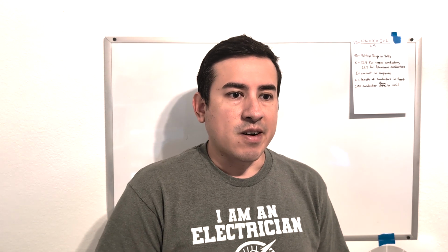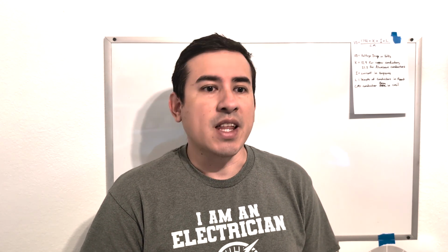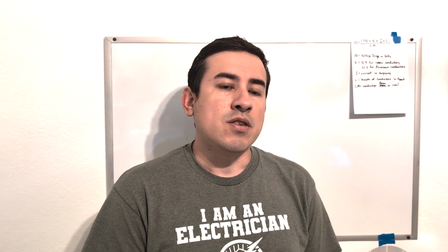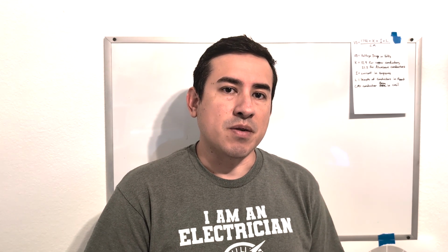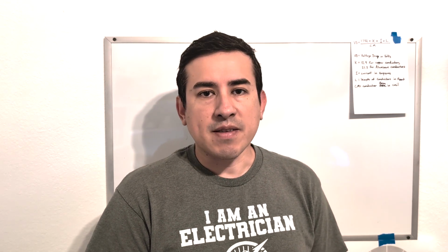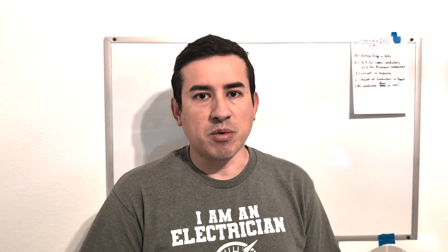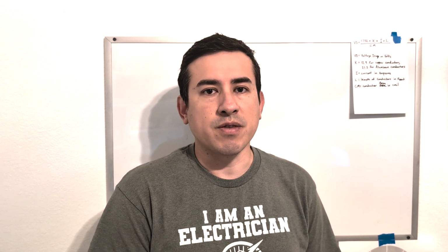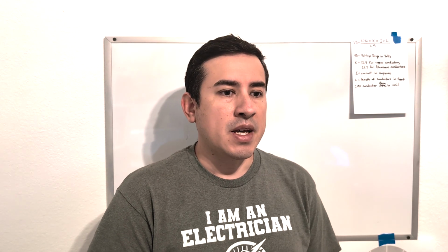This is referenced in Article 210.19, informational note, and then again in 215.2(A)(2), informational note number 2. So it's mentioned in there twice, and basically both say the same thing. Feeders 3%, branch circuits 3%, with a combined total voltage drop no more than 5% on the whole circuit.